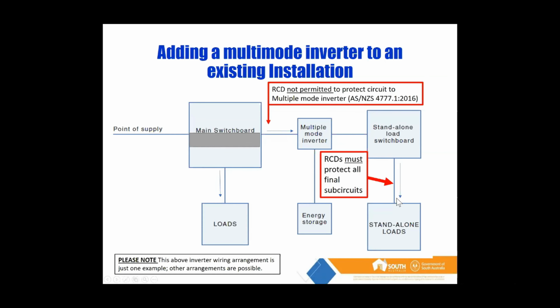The second thing that I need to reaffirm is when you are installing a standalone switchboard or standalone supplies off a multimode inverter, those standalone supplies have to be on RCDs. And the reason is when we're getting fed from, let's say, an engine-driven generator, or from the grid, wherever you're getting fed from, the amount of available fault current there is incredibly high. It's going to be enough to operate our protective devices within the required time. If we're getting fed by a small little battery on the side of someone's home, we're potentially not going to have that fault current available. So an RCD is required.